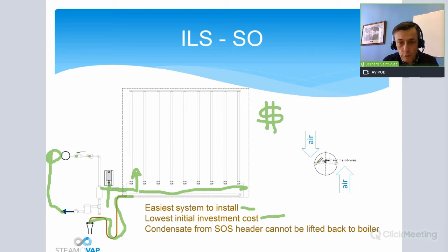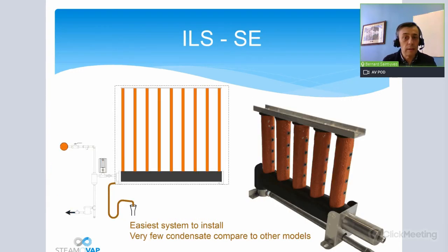Just to remind you that, of course, the nozzles in this case are perpendicular to the airflow, always, okay, for the SteamOsorb. So then you have one easy way to limit the losses. You put insulation on the tubes, okay, on the distributor. This is our version of the high efficiency steam distribution, which is the same way for pressurized steam or atmospheric steam. So it's the same circuit again, and again the condensate will go here to drain. You are limiting a lot the condensate going to the drain, so the losses. Okay.